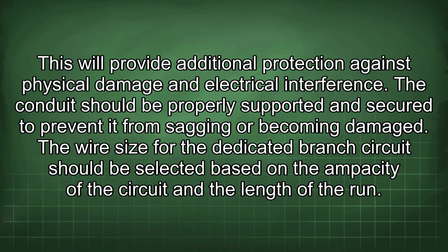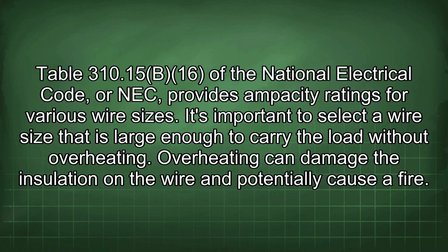The wire size for the dedicated branch circuit should be selected based on the ampacity of the circuit and the length of the run. Table 310.15(B)(16) of the National Electrical Code, or NEC, provides ampacity ratings for various wire sizes. It's important to select a wire size that is large enough to carry the load without overheating. Overheating can damage the insulation on the wire and potentially cause a fire.